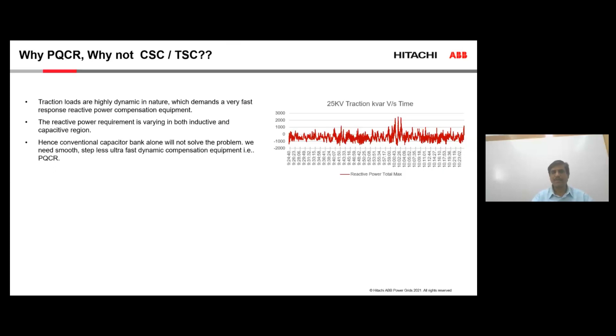When we talk about some traditional systems, which are capacitor switched or thyristor switched capacitor solutions, they can give a solution in the capacitive region, but they cannot give a solution in the inductive region. That is why, when we talk about the latest power electronics based PQCR, as we call it, it can give correction both on the inductive side as well as the capacitive side. So now, therefore, we say that only capacitors, fixed capacitors, or for that matter, switched capacitors will not be able to solve the complete problems that we face in metro and high-speed rail. What we therefore need is stepless, ultra-fast dynamic compensation that can work both in the inductive region and the capacitive region, and that solution is the most ideal, and we call that PQCR.